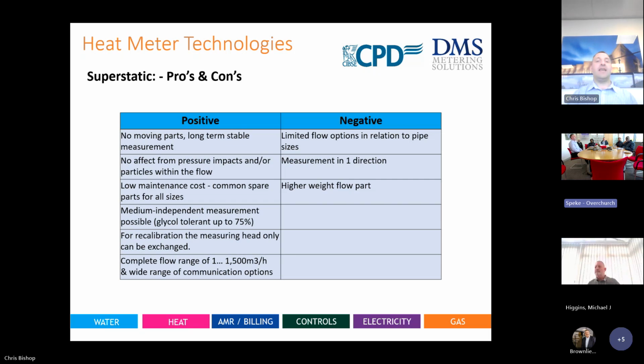The point of that is obviously the independent measuring possible with glycol, because it was used on really cold liquid nitrogen systems a long time ago, and it's been redesigned over many years. These meters are generally used now around European continents involving cold climates. So Sweden, Finland, Norway, where heat pumps are very common. District heating is by far very common, but they generally have glycol in the system at large concentrations because of the outside temperatures during winter. So you can program that glycol on site. You can obviously order the meter based on a glycol parameter. Yet again, that gets to what I was saying about on-site support and programming and guiding people through it.